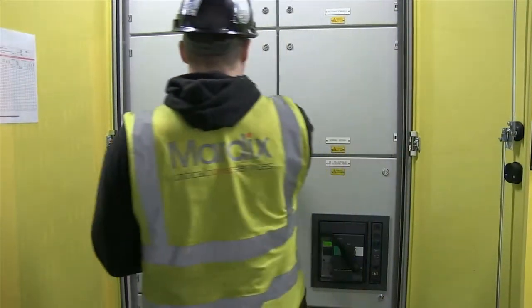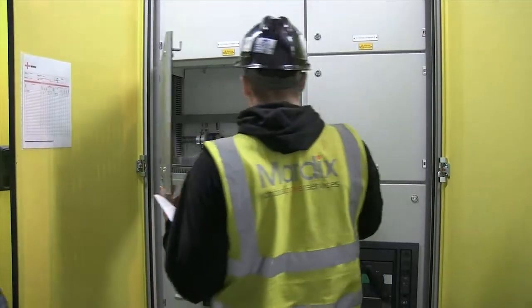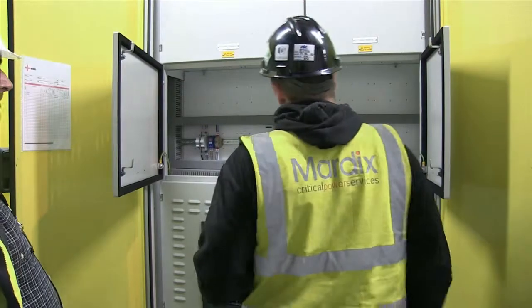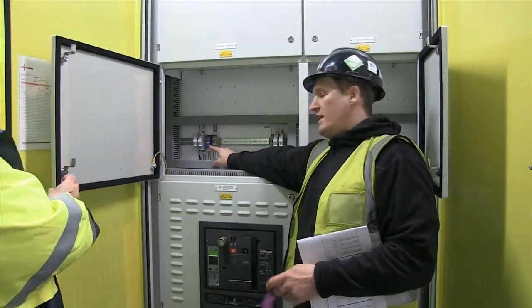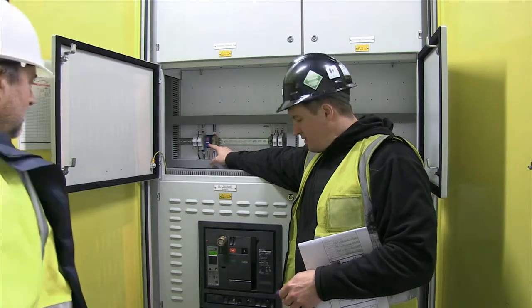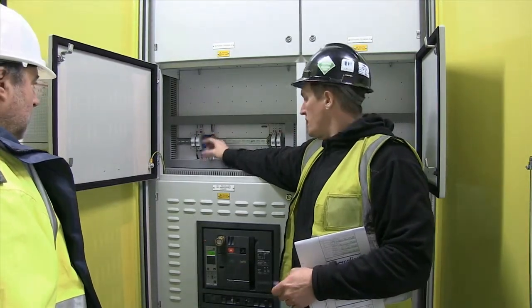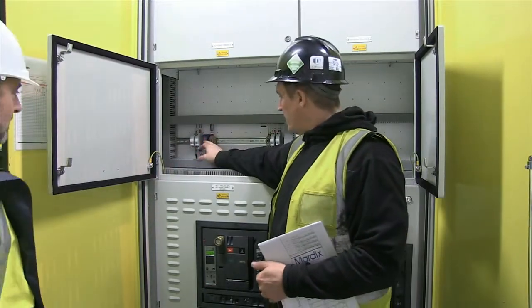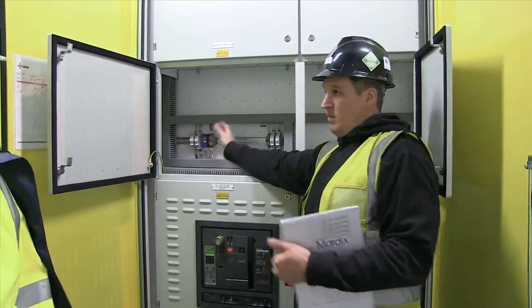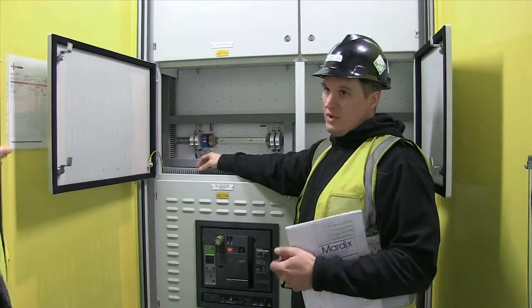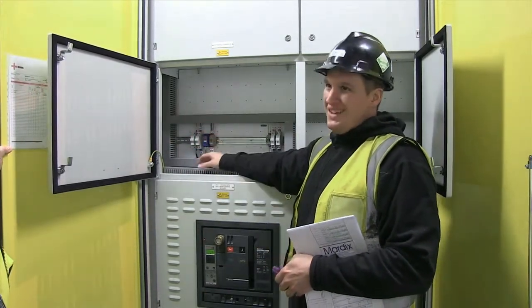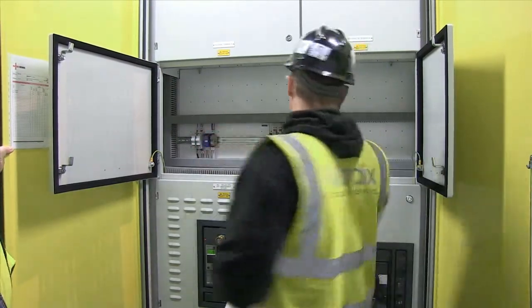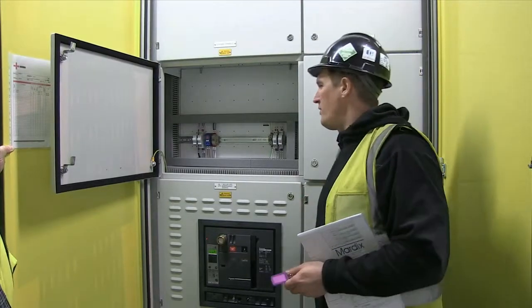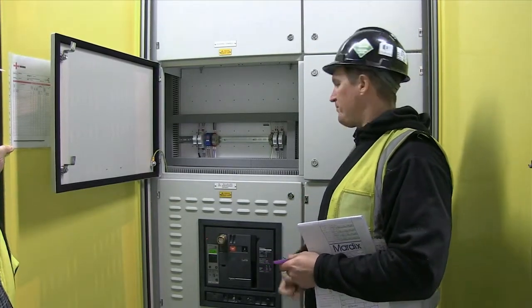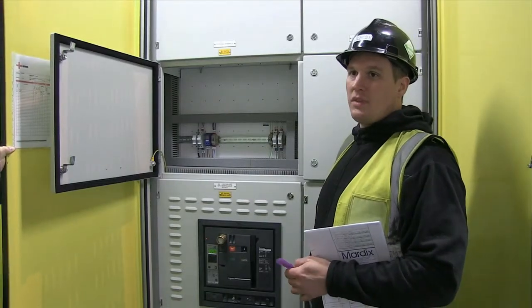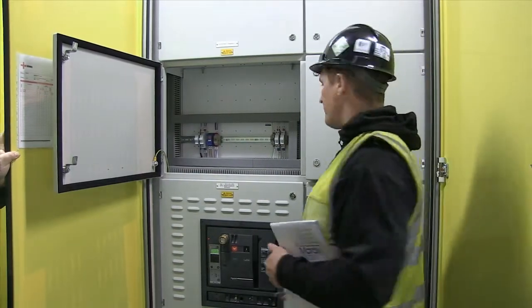What you'll find in here, most sections will have a thermostat. So that thermostat is, you probably won't use it so much now, but if it's very, very cold, there's little heaters in every single section. So if you wanted to keep the panel at 30 degrees, turn it to 30 degrees. When it drops below 30 degrees, the little thermostat heaters will kick in. They're only tiny little things, but you know, just keep it. So it's just anti-condensation. Yes, exactly, anti-condensation. Once it gets back up to 30, it'll kill itself off.